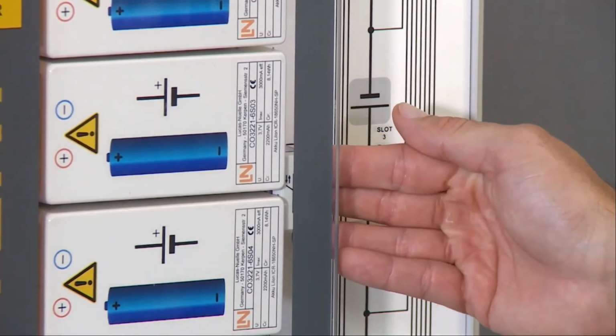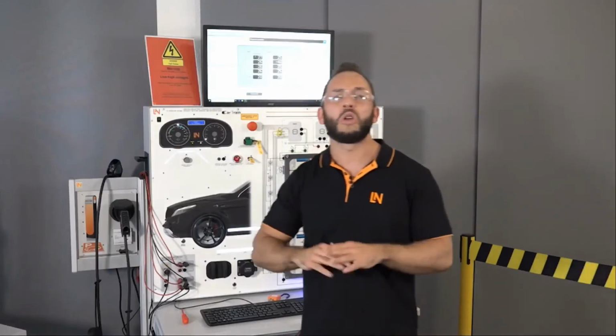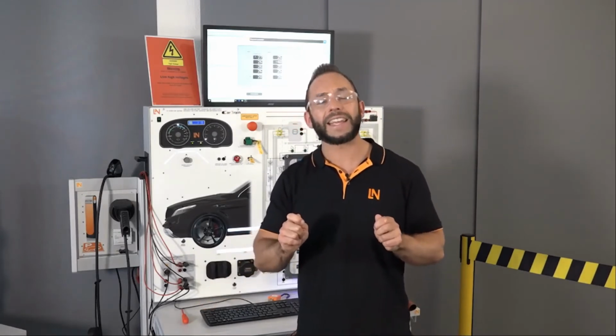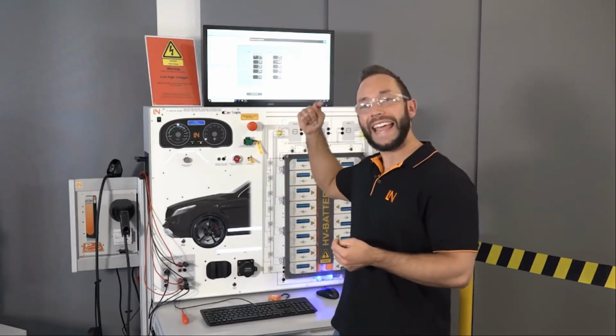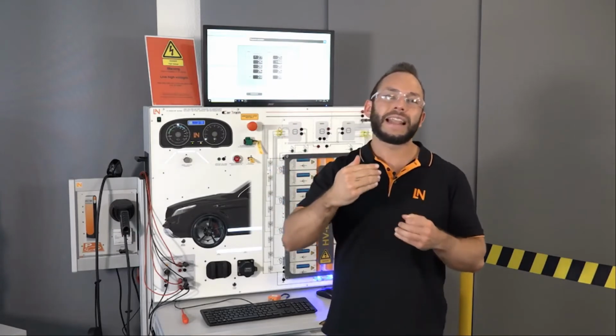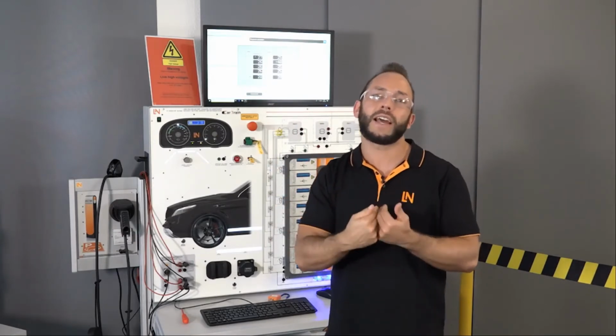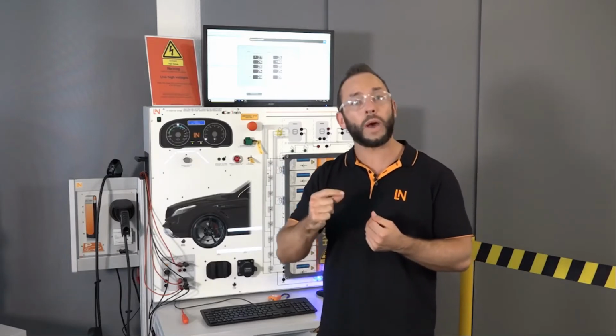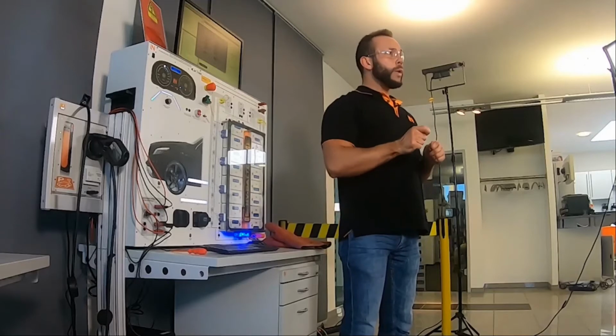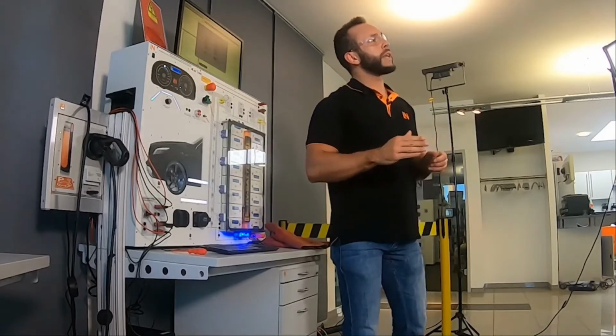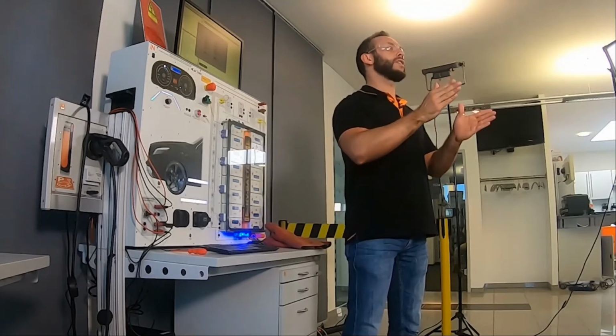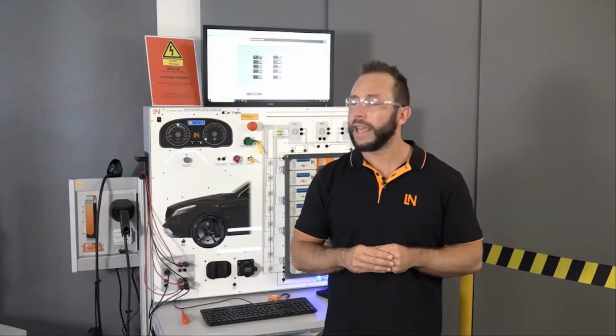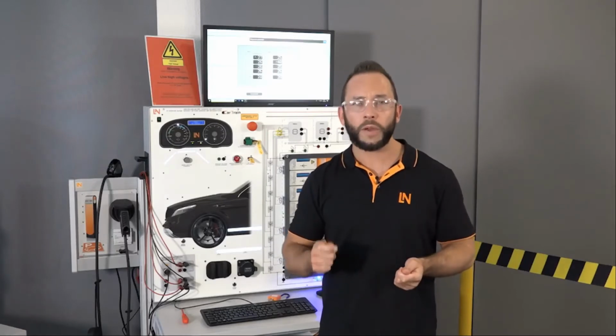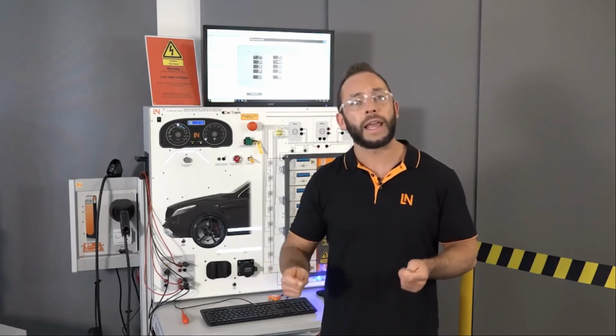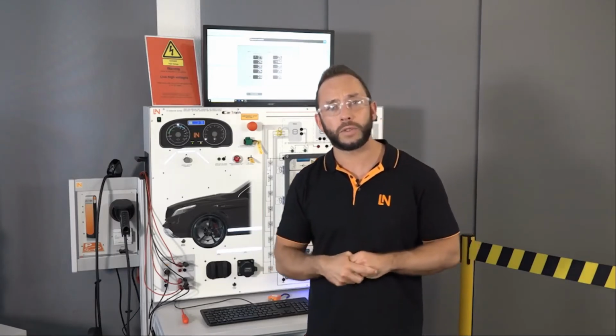So what does this temperature tell us now? At minus 40 degrees, no fire will start. But we can say it's a non-critical fault at that stage. Why can we say that? Because it means that this NTC temperature sensor has something like a disconnect or interruption inside the wiring or inside the sensor itself. This is why it shows minus 40 degrees. Now we know that this is a non-critical fault. That means we can bring the car inside the workshop, open the battery and repair it. In order to open the high voltage battery, we have to shut down the high voltage beforehand. And I will show you now how we can do that on that system as well.